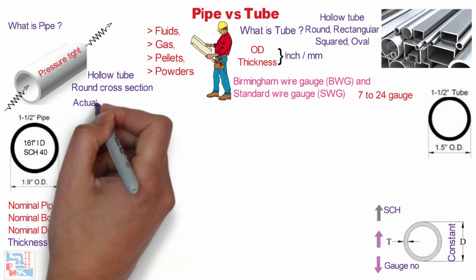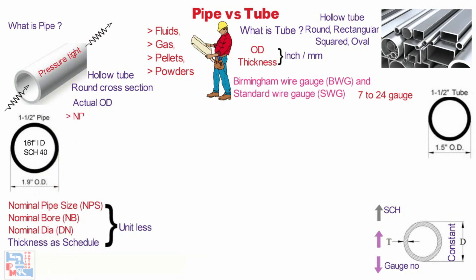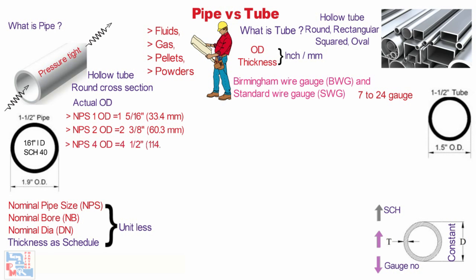Let's see the actual outside diameters of pipe. NPS 1 inch has an actual OD of 1 and 5/16 inches, that is 33.4 mm. NPS 2 has an actual OD of 2 and 3/8 inches, that is 60.3 mm. NPS 4 has an actual OD of 4.5 inches, that is 114.3 mm. NPS 14 has an actual OD of 14 inches, that is 355.6 mm. From NPS 14 onwards, OD matches with the NPS size.